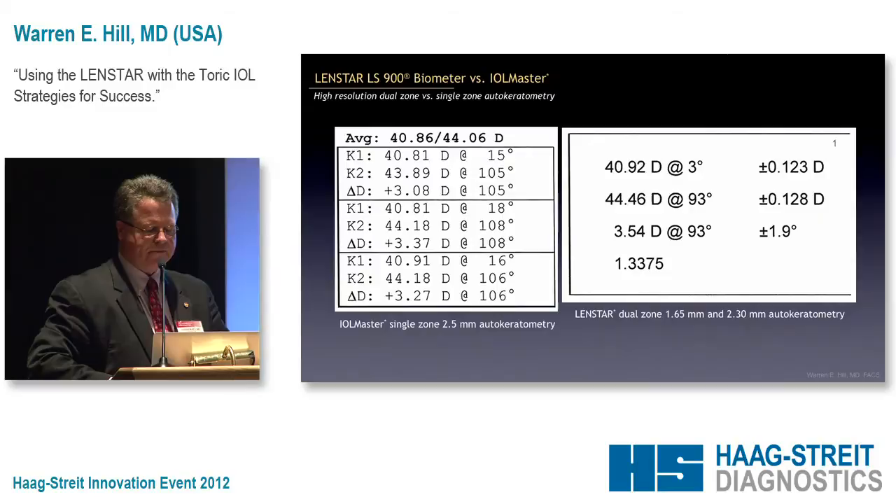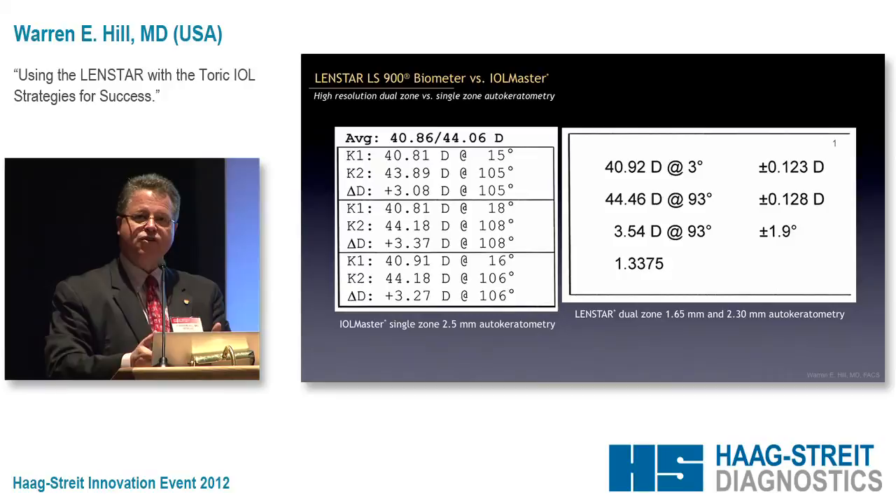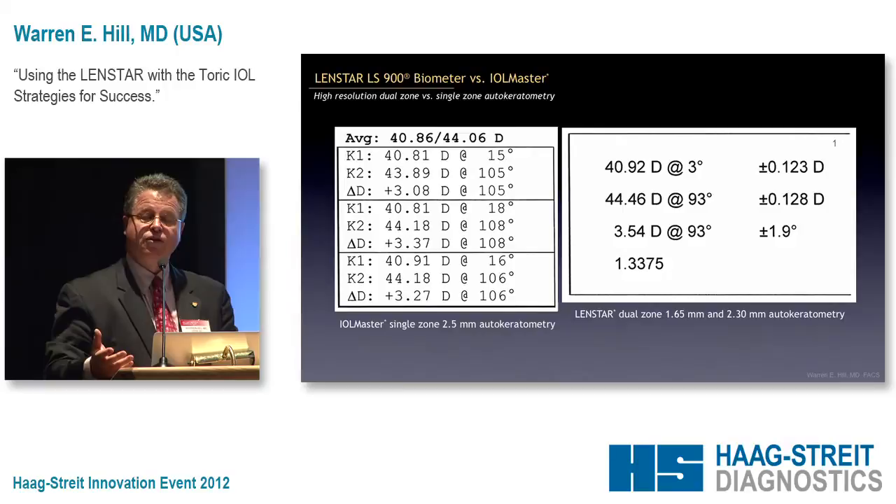Let's do a quick example. This is one of my own patients — a set of measurements with the IOLMaster and a set with the LENSTAR. If you look at the magnitude of astigmatism, it's within a quarter diopter, so most people would say that's pretty good agreement. But if you look at the approximation of the steep and flat meridians, you can see that they don't coincide, and this is a very common story told over and over again with the IOLMaster.